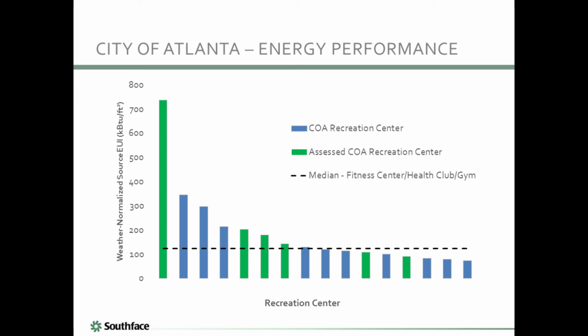For reference, a typical office building has a median site EUI of 54 kBTUs per square foot and a median source EUI of 167 kBTUs per square foot. So a recreation center consumes a bit less than an office building. The median source EUI for City of Atlanta recreation centers is 124.8, pretty much identical to the national median. However, there's significant variation. Half of the recreation centers in this portfolio are performing worse than the national median, and half are performing better.